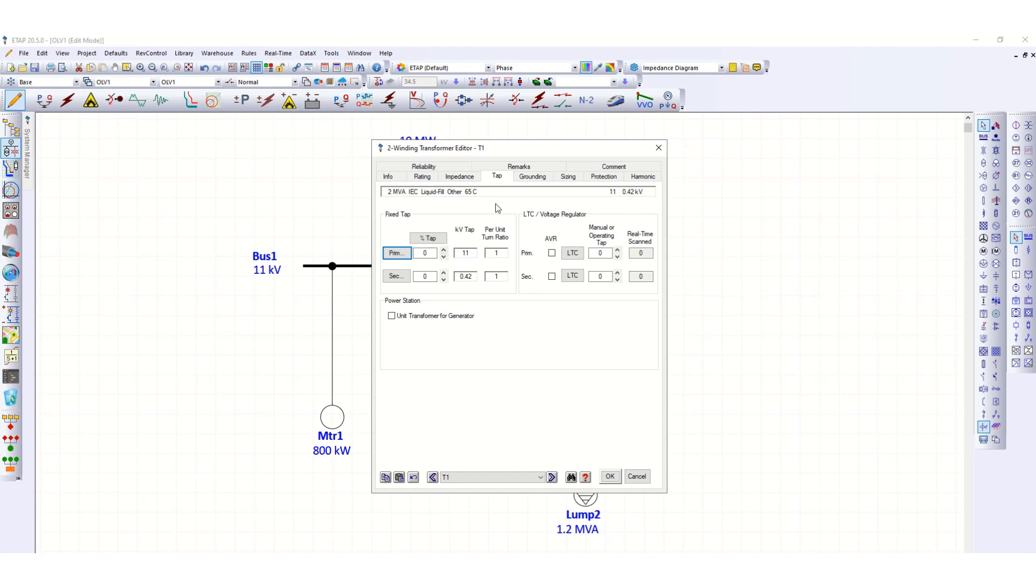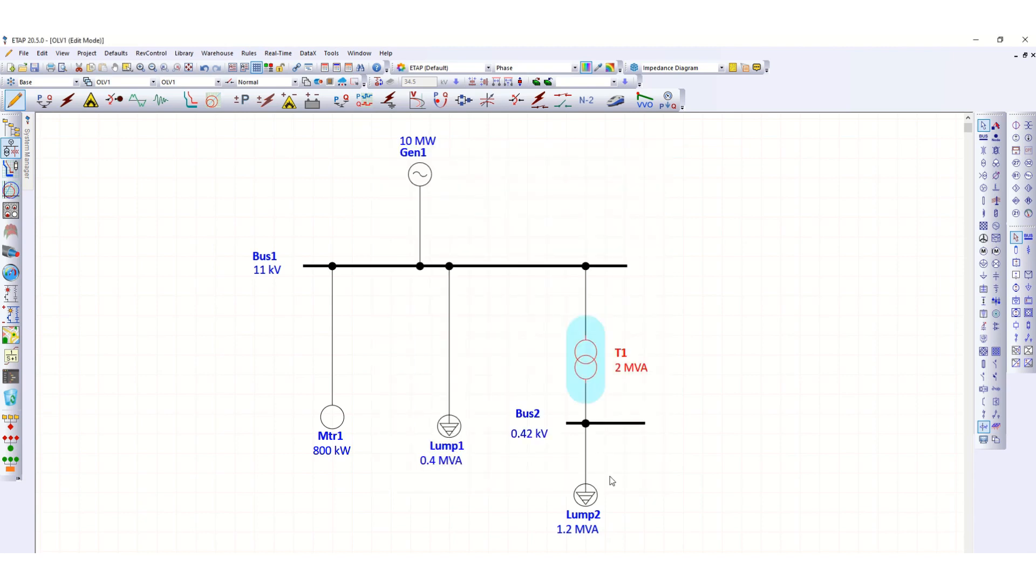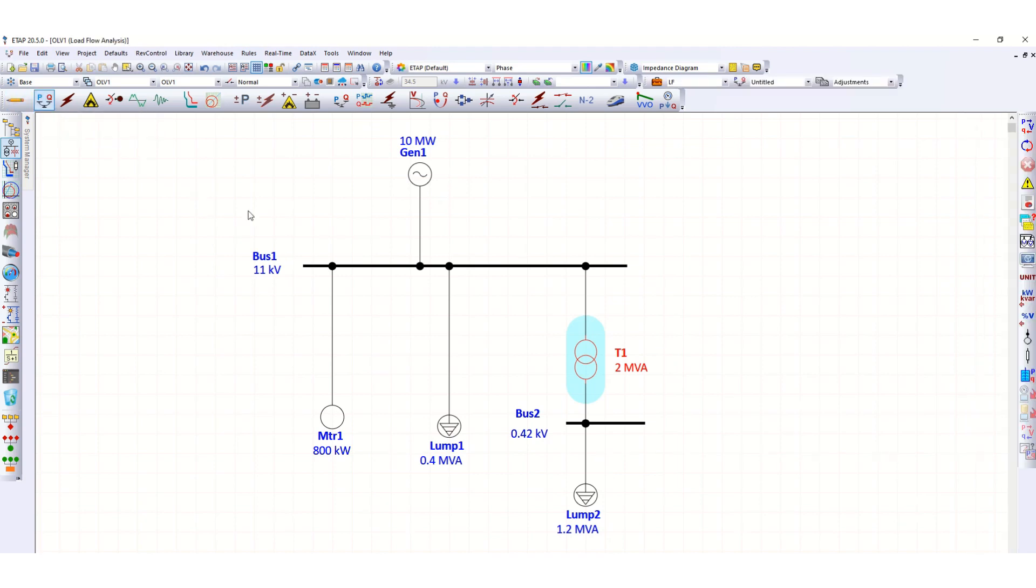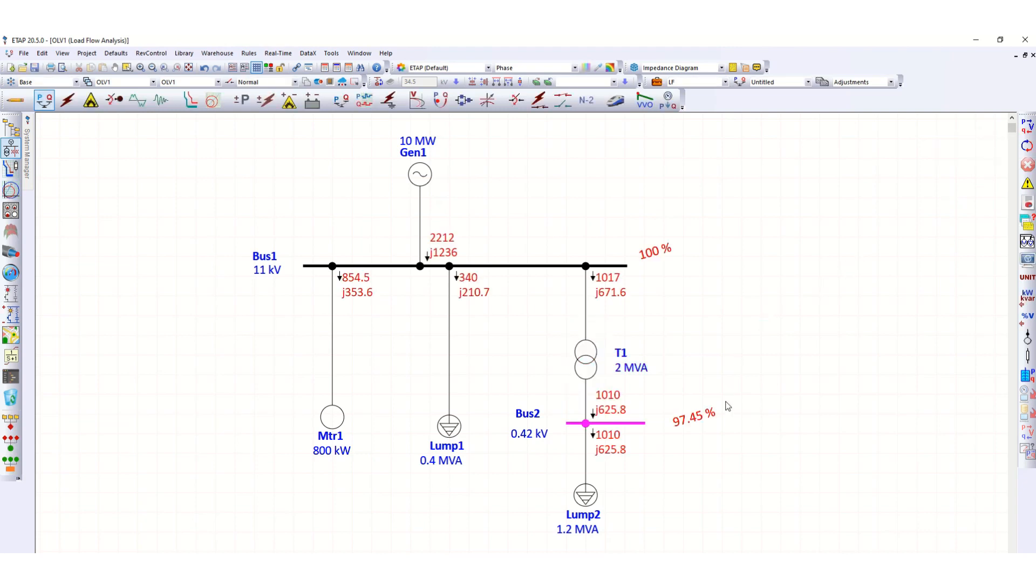So let's check first not using that transformer tap changer. It is set at 0 tap. Let's click OK. Now let's check the load flow. If we run the load flow, okay, now as you can see this bus voltage is 97.45 percent.